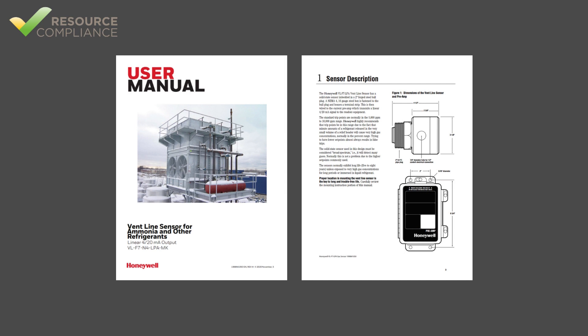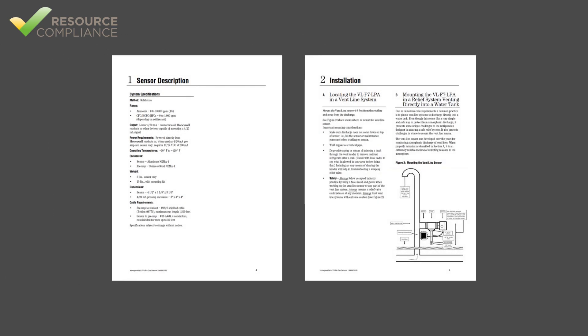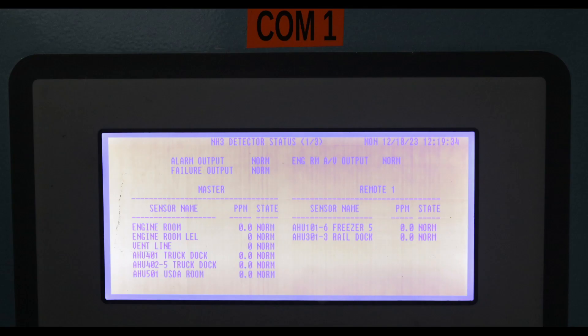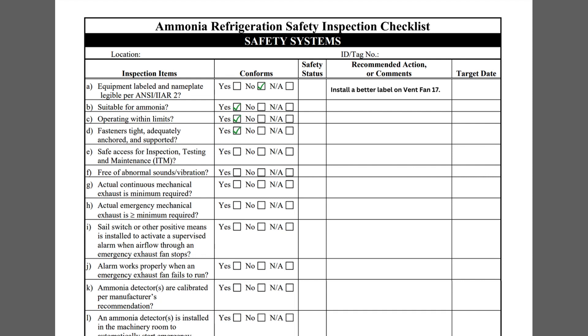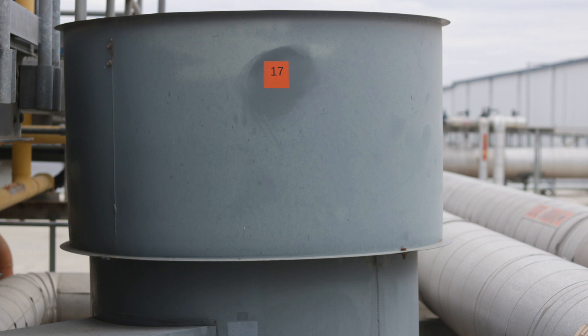Items B and C ask if the safety system's equipment is suitable for ammonia and operating within limits. Suitability for ammonia can be verified by the equipment specifications provided by the manufacturer. For safety systems, the most relevant operating limit is the ammonia concentration, which can be monitored at the PLC HMI. Item D requires the inspector to verify that supports and anchorage are adequate. This fan is installed on a properly designed roof curb.